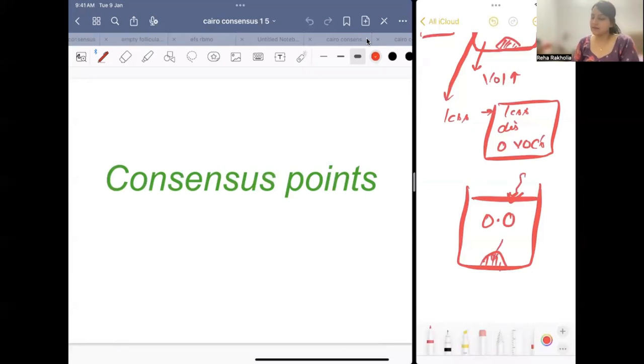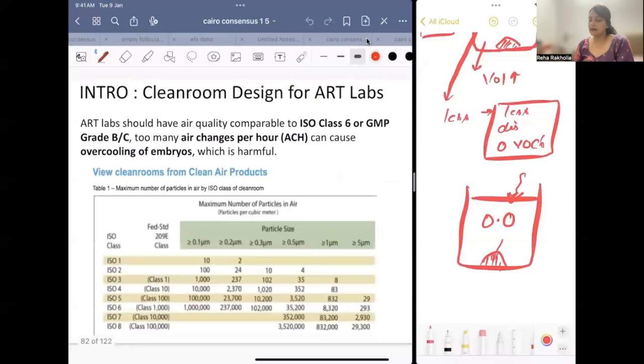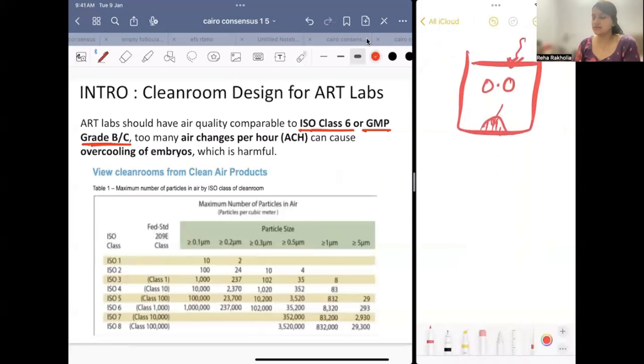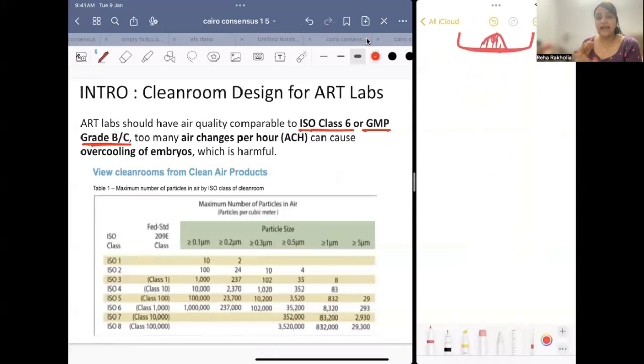Now consensus points. Clean room design for the ART lab. The ART lab should have air quality comparable to ISO class 6 and GMP grade B/C. But in ISO class 6 and GMP grade B, there are many air changes, and in an IVF lab we do not want that many air changes. These classifications were made for surgical suites, but we are talking about ART suites. We don't need that many air changes because that will cause cooling of the embryo. We need fewer air changes. So for the particle size, we can say that we'll use ISO class 6 and GMP grade B and C.